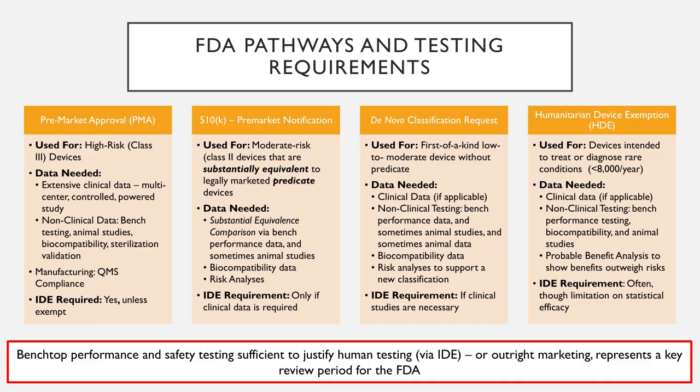And you can argue that, therefore, you are equivalent to that device. So it's an argument saying you're just as safe as other devices, not necessarily that your device is, in absolute terms, safe and effective. Now, the data needed is anything that can demonstrate substantial equivalence to that prior device. So you're no longer talking strictly on efficacy and safety per se. It's simply equivalence testing to those predicate devices.